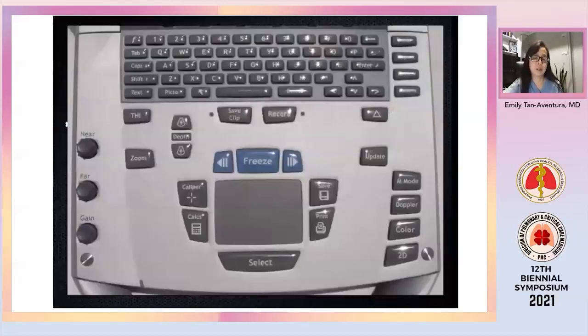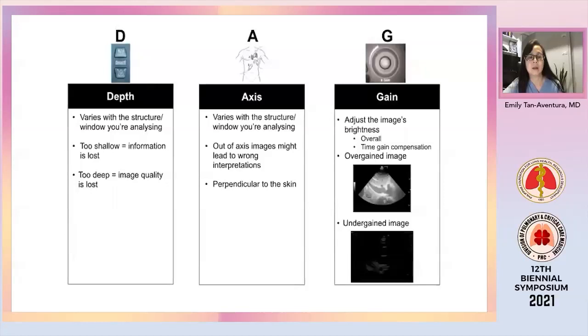This is an example of one of the ultrasound machine knobs and buttons. Don't be overwhelmed by this. All you have to be familiar with, at least for the basics of ultrasound, is the depth button to adjust and the gain. For the depth, you just need to make sure that your image is in the middle of the screen. Too shallow, you will lose information. Too deep, you might lose image quality. As for the gain knob, with over gain, you will have a wash out of the image. And with under gain, your image will be dark. So you'll just have to adjust the gain as you see the visibility on the screen.